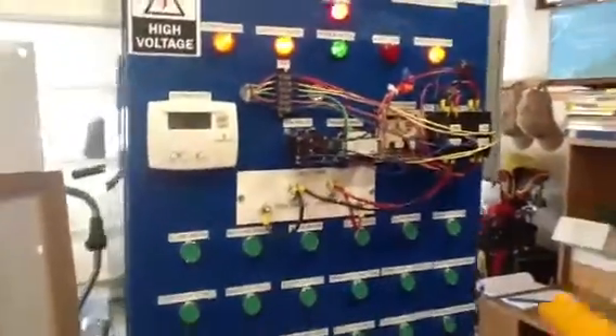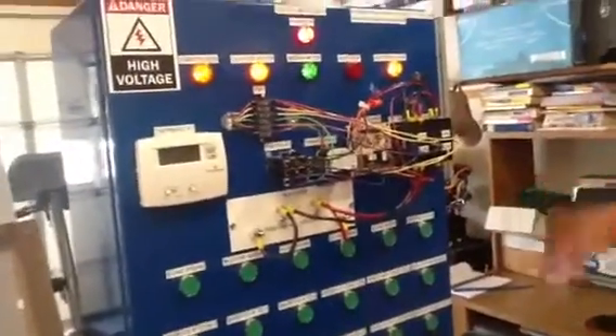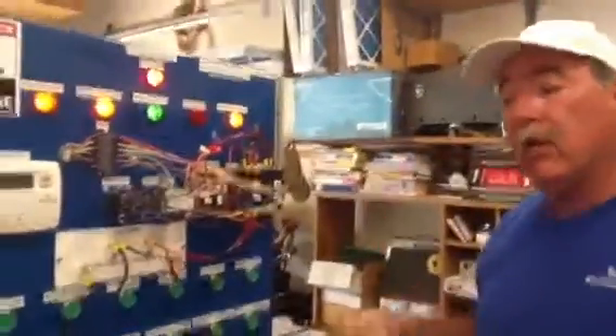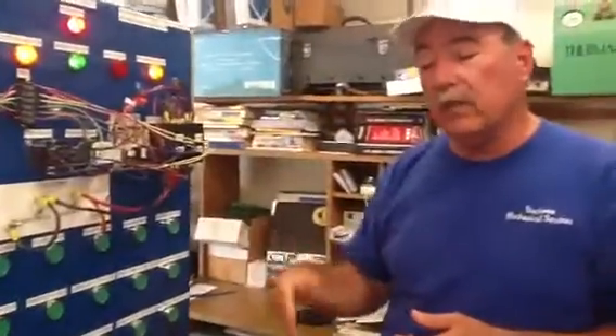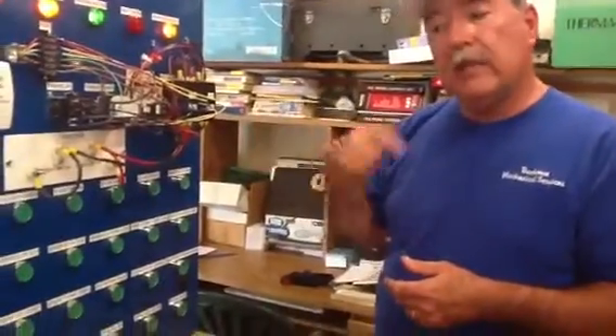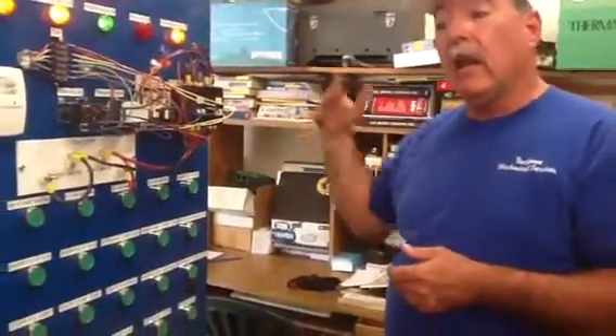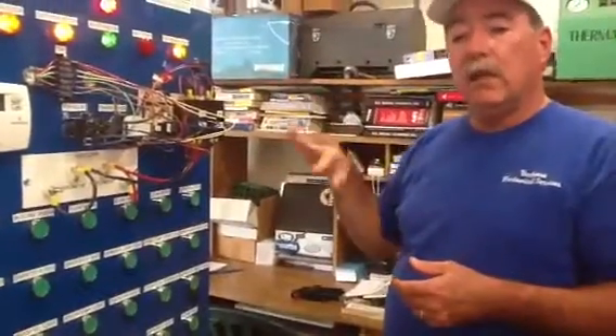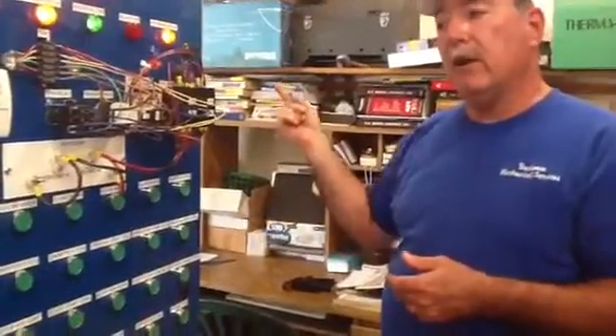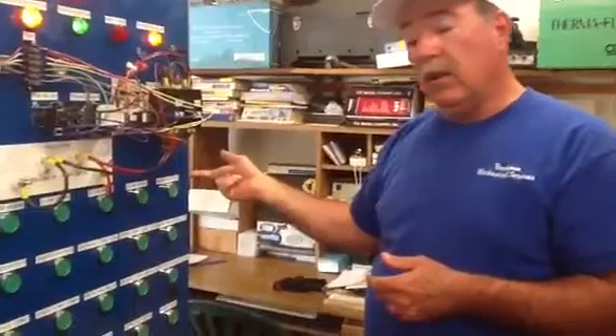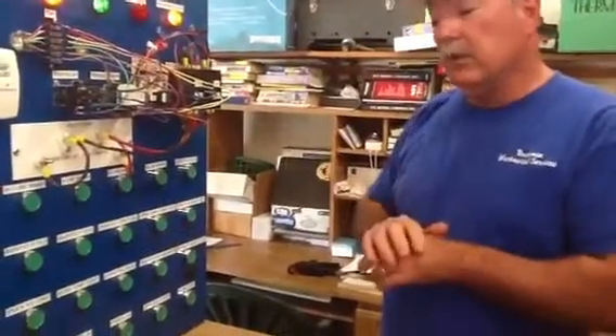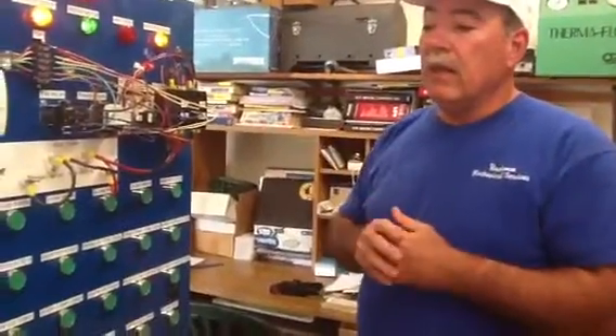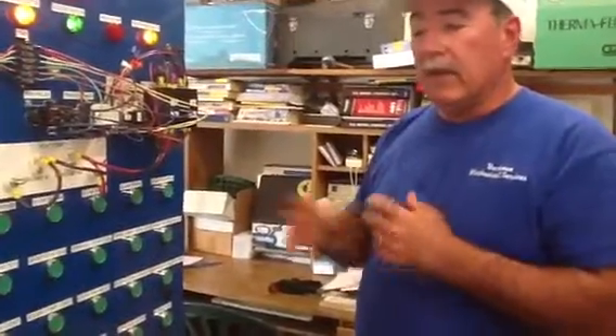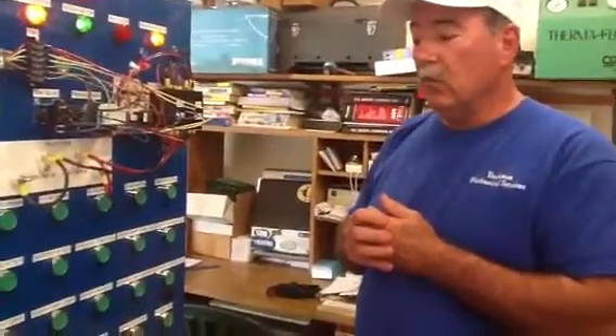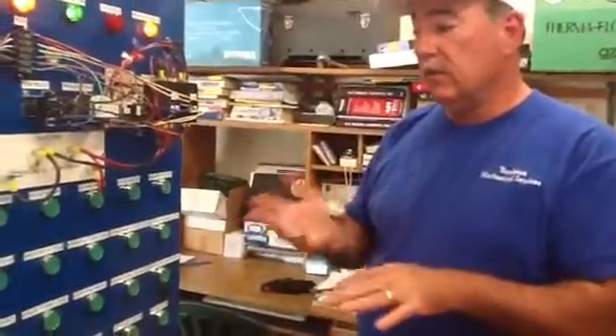Now the blown fuse actually alternates. If you power down and power up, it would always start with phase B. If you push blown fuse again, it would be phase A, and it will alternate each time until you power down and power back up at the 110 volt switch here, or unplug, whichever comes first. That's how that particular problem works. It alternates between the two fuses.